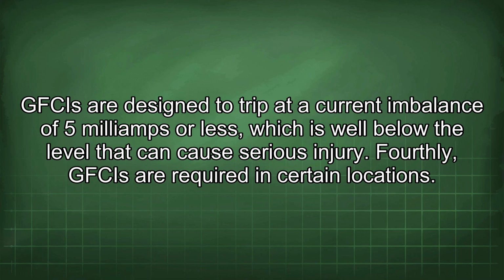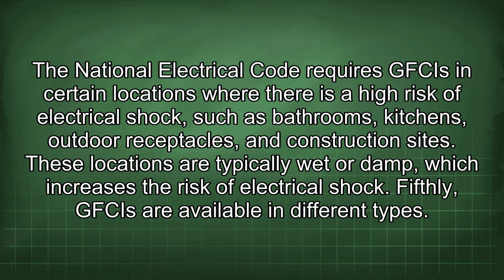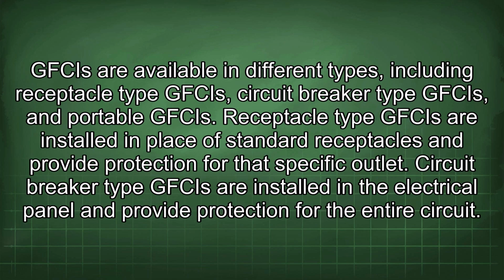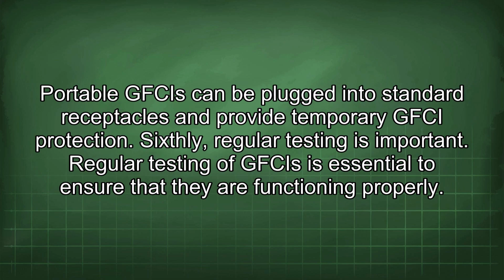Fourthly, GFCIs are required in certain locations. The National Electrical Code requires GFCIs in certain locations where there is a high risk of electrical shock, such as bathrooms, kitchens, outdoor receptacles, and construction sites. These locations are typically wet or damp, which increases the risk of electrical shock. Fifthly, GFCIs are available in different types, including receptacle type GFCIs, circuit breaker type GFCIs, and portable GFCIs. Receptacle type GFCIs are installed in place of standard receptacles and provide protection for that specific outlet. Circuit breaker type GFCIs are installed in the electrical panel and provide protection for the entire circuit. Portable GFCIs can be plugged into standard receptacles and provide temporary GFCI protection.